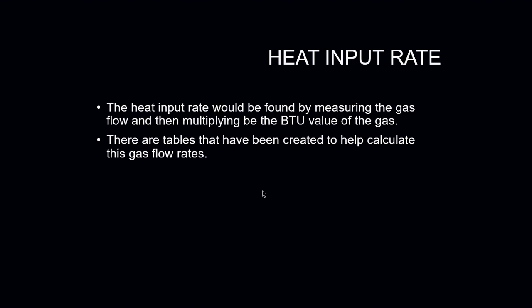Heat input rates all culminate in what we've been discussing. The heat input rate is found by measuring the gas flow and then multiplying it by the BTU value of the gas being used. There are tables that have been created to help calculate your gas flow rate, so you don't constantly have to use a calculator. A lot of furnaces will have charts in their literature to help you figure this out.